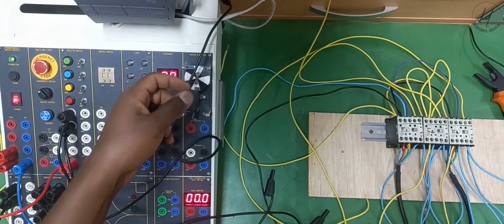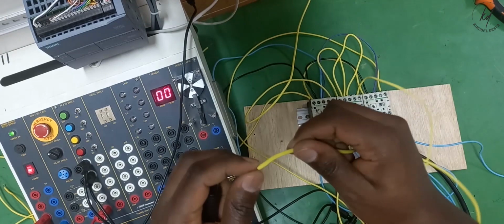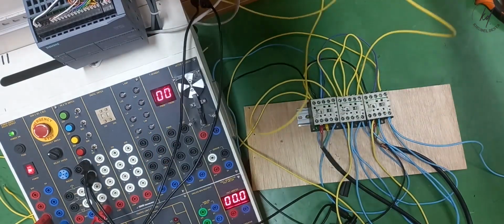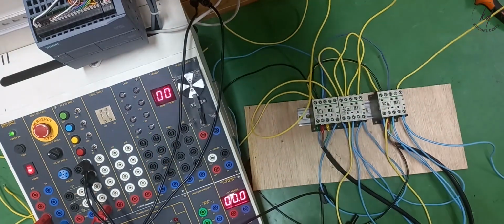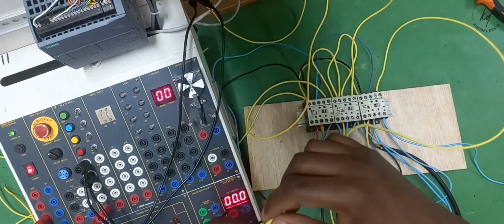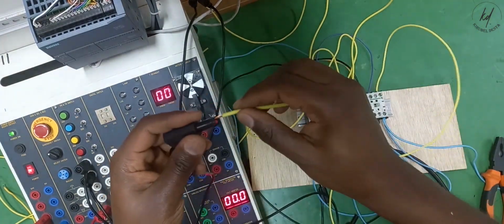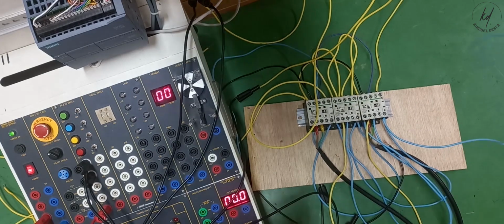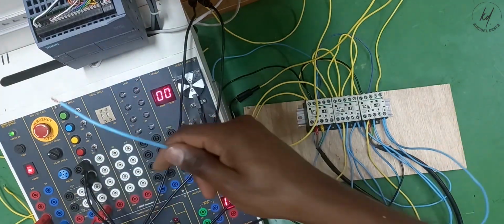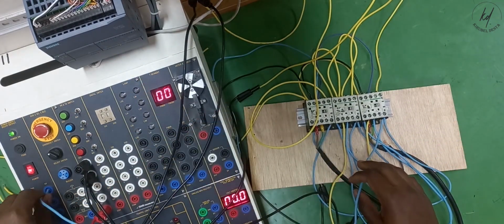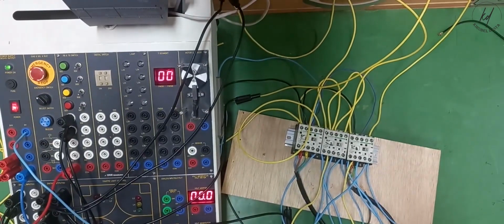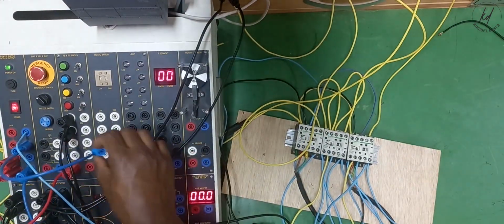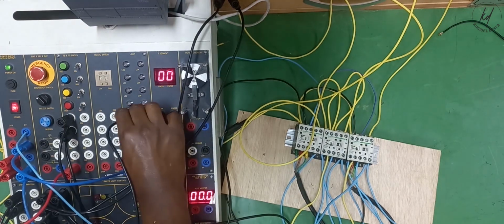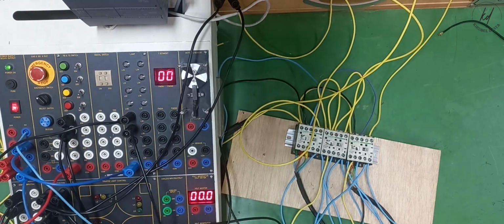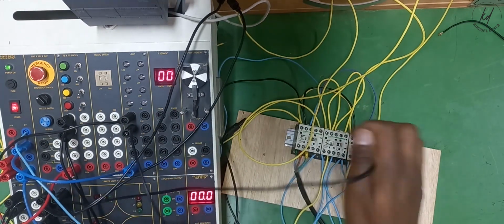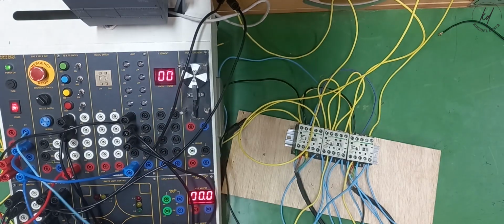Operating principle of a contactor: the current passing through the contactor excites the electromagnet. The excited electromagnet produces a magnetic field, causing the contactor core to move the armature. A normally open NO contact completes the circuit between the fixed contacts and the moving contacts. This permits the current to pass through these contacts to the load. When current is removed, the coil is de-energized and opens the circuit. The contacts of the contactors are known for their rapid open and close action.